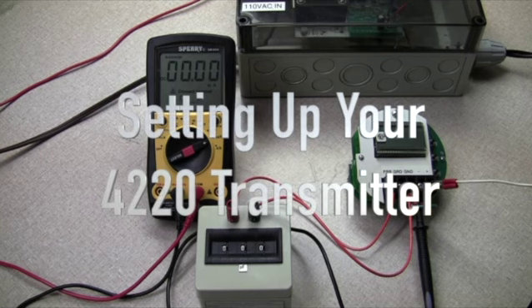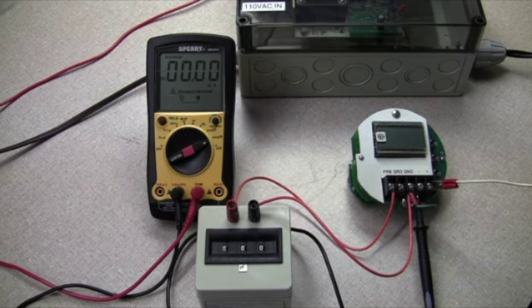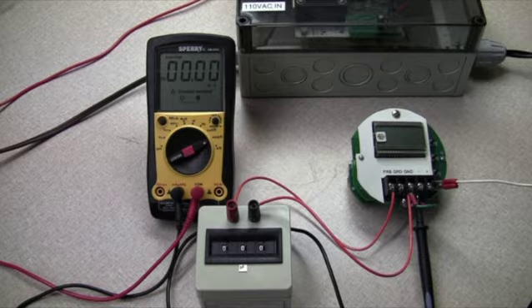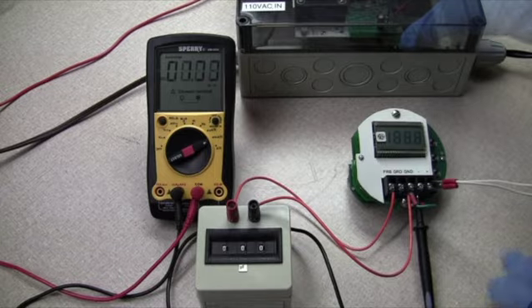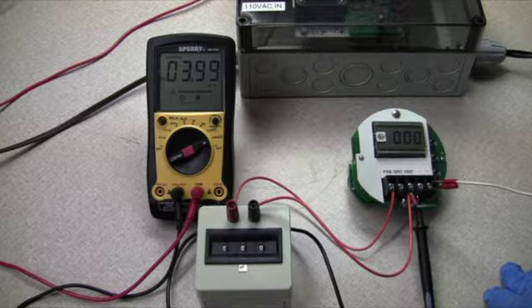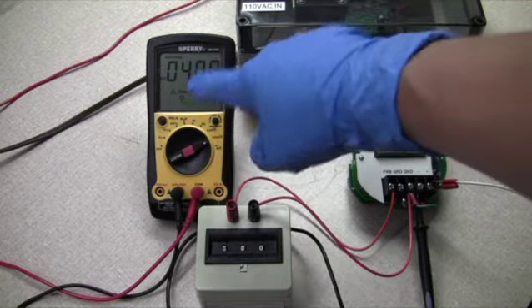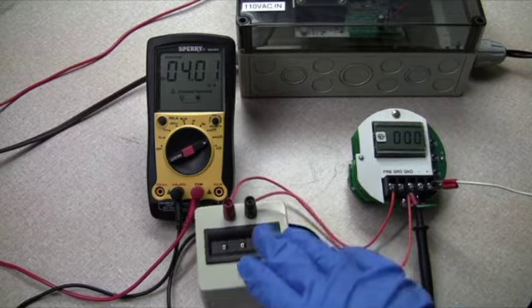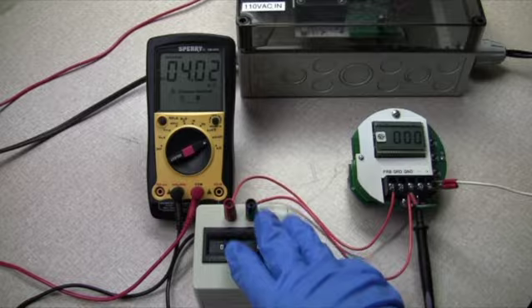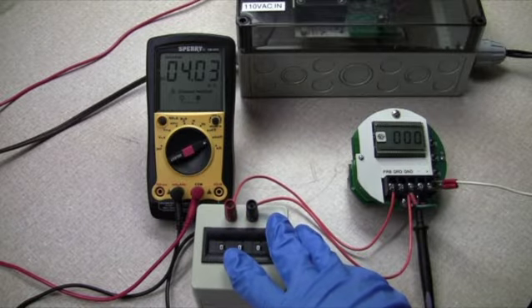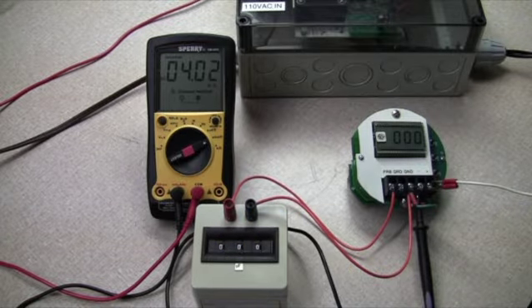Today we're going to be looking at the 4220 transmitter board and how to calibrate it and set your high and low. First we need to power it up. 24 to 28 volt DC loop. When you're in the loop, this is just for reference, so we're looking at the 4 milliamp signal. Our capacitance substitution box takes the place of liquid in your tank, and of course our transmitter board.